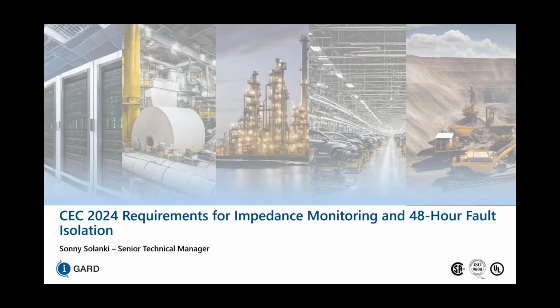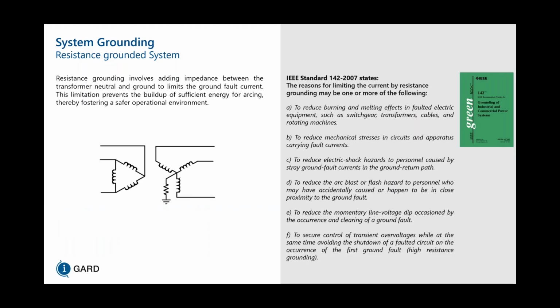So today's presentation will be on the Canadian Electrical Code 2024 requirements for impedance monitoring and 48-hour fault isolation. And let's begin with what a resistance grounded system is. Resistance grounding involves adding impedance between the XO point and ground, which allows for the resistor to be in series with the ground fault that would be in the system. In that case, the ground fault current gets limited by this resistor, and this limitation prevents the buildup of sufficient energy for arcing, thereby fostering a safer operational environment.